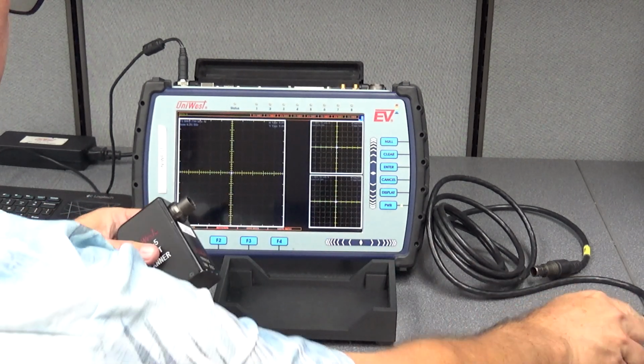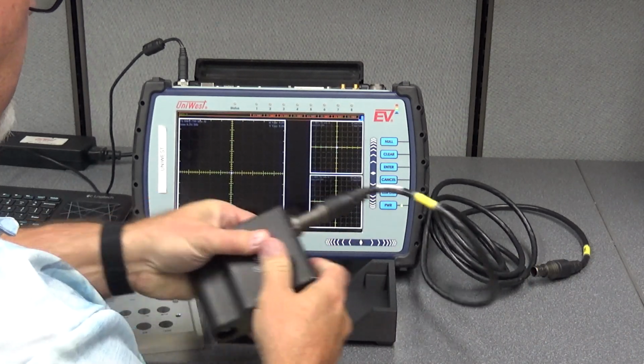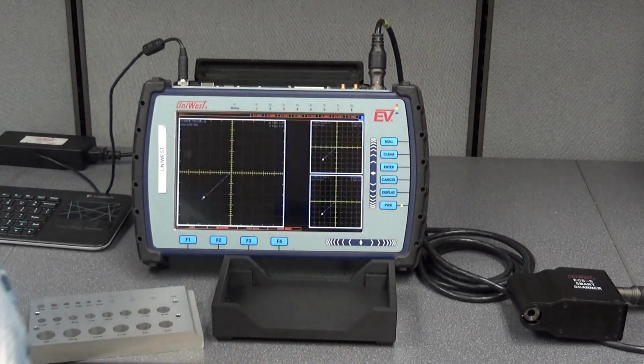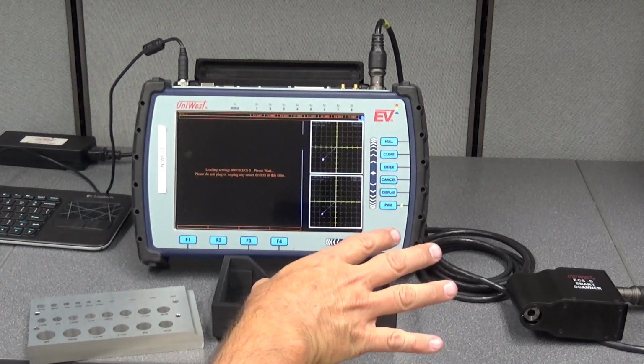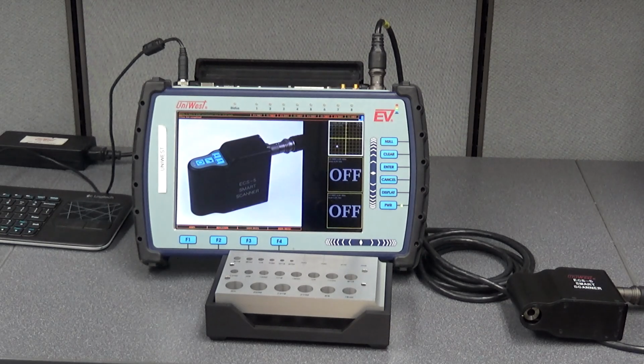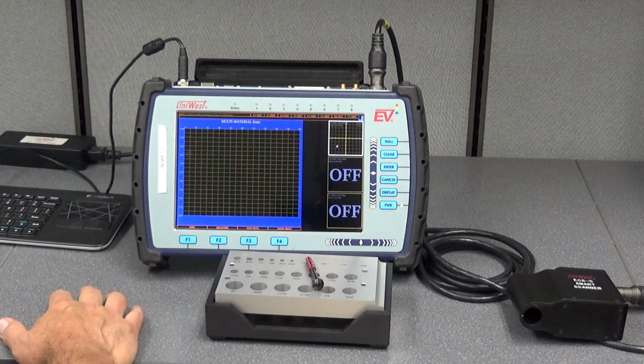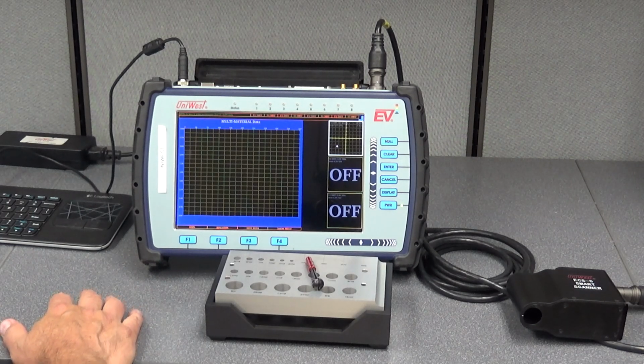First thing we'll do is connect the ECS-5 scanner to the cable. And the other end of the cable we're going to connect to the probe connector on the top of the instrument. The instrument will auto-recognize that we have an ECS-5 scanner connected. And at this point it will load in the appropriate initial settings for the scanner. So once this is all done, then we could actually manually go through the process of setting up the gain and rotation and liftoff and whatnot. But we're going to actually use the auto calibration script that's built into the instrument.